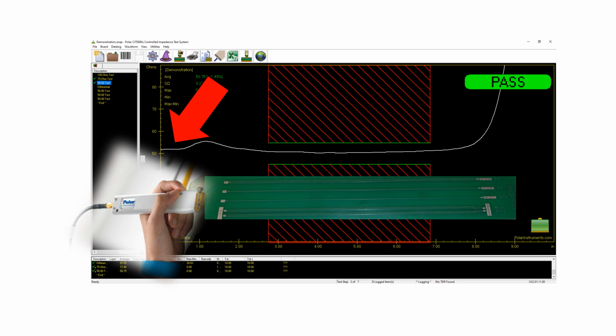Again, this is the launch aberration. You need to compress the probe tightly to the board to make sure that's kept as small as possible. And here is the rise to the open circuit at the end of the trace. And when you're setting limits, you need to keep clear of these two areas to make sure you get a good impedance test.